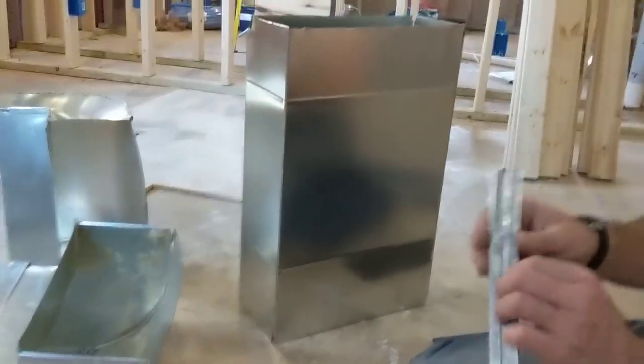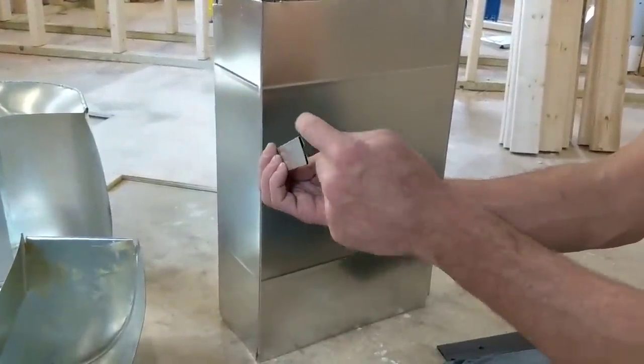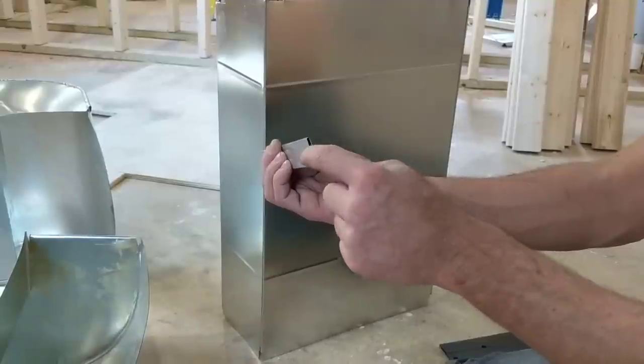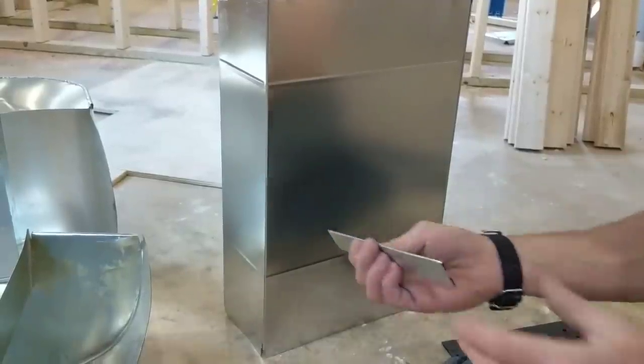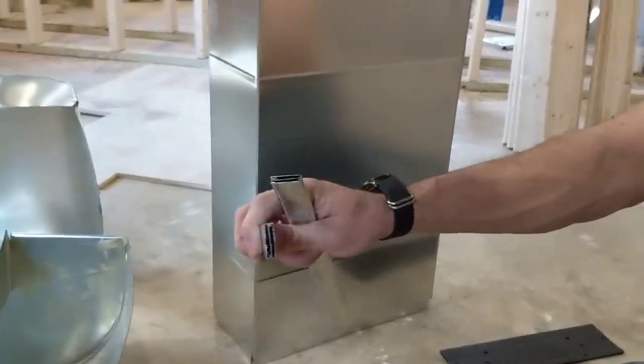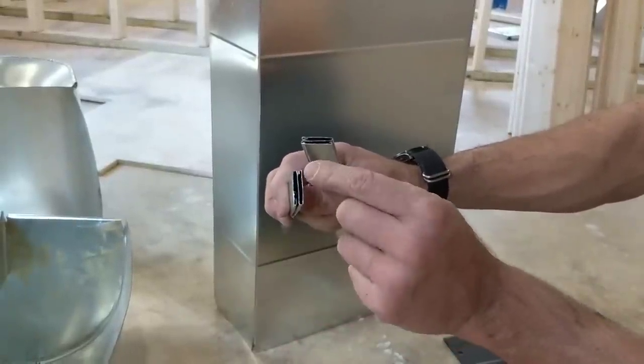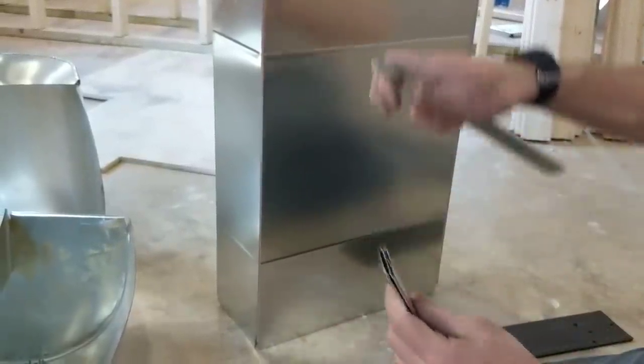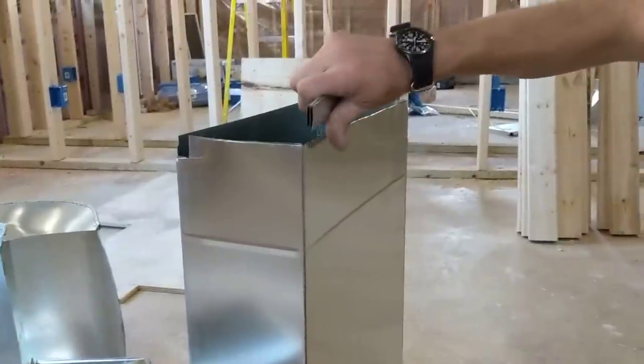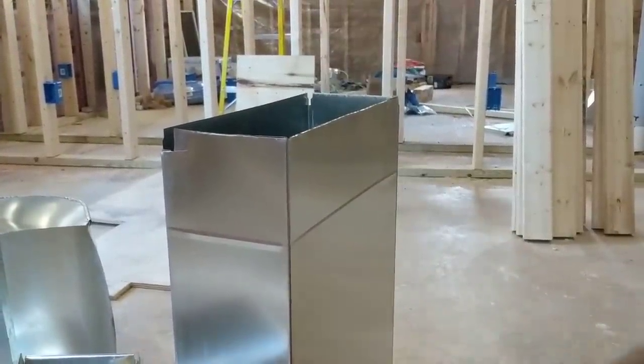The way these ducts go together is really quite ingenious. There's a drive cleat, which is a C-shape — it's just bent up here and bent around here. And there's also an S cleat. This is basically an S shape; it has a little fold over here and a fold over there. The S cleat slides right on top of a duct and the drive cleat goes on the side — I'll show you how in just a sec.